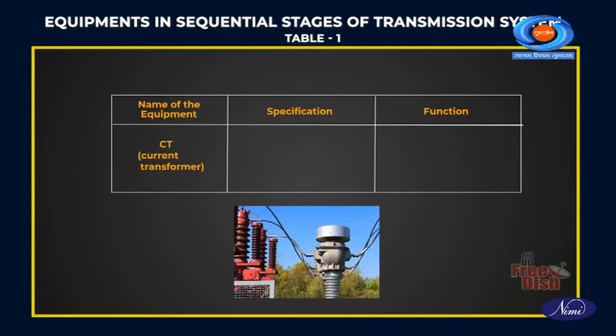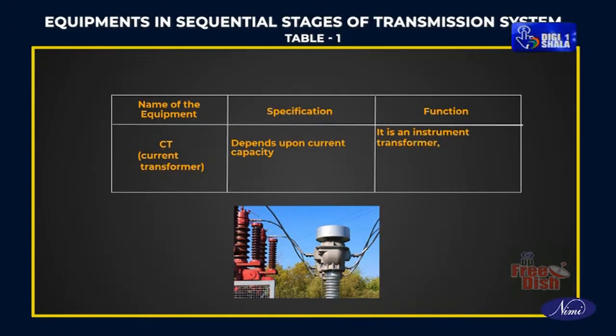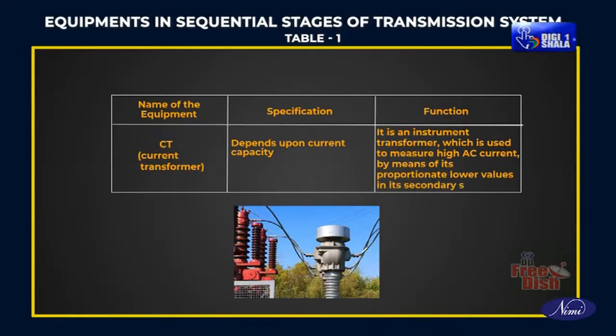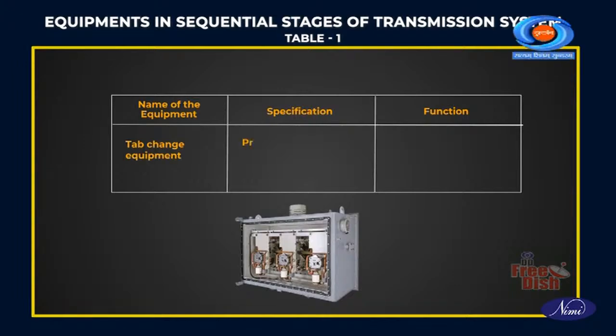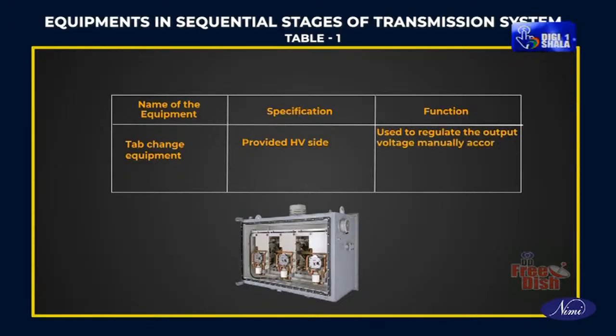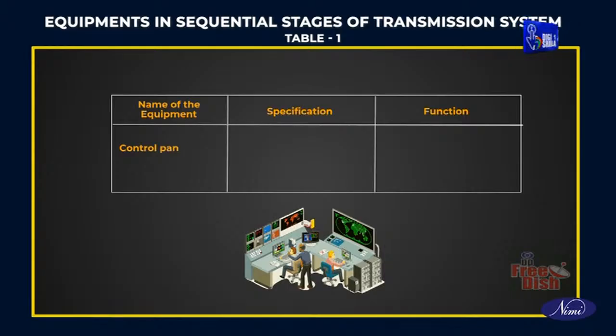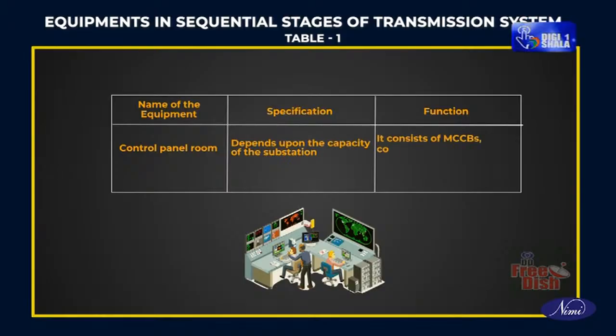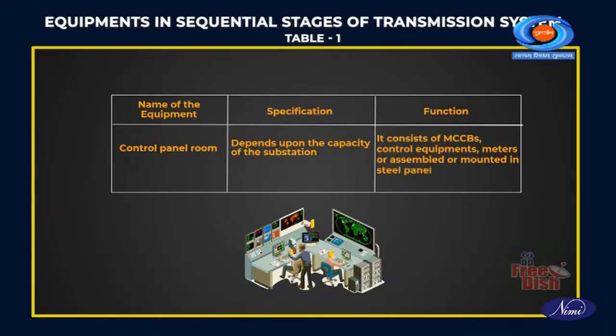CT or current transformer depends upon current capacity. It is an instrument transformer which is used to measure high AC current by means of its proportionate lower values in its secondary side. Tap change equipment provided HV side, used to regulate the output voltage manually according to the line voltages. Control panel room depends upon the capacity of the substation. It consists of MCCBs, control equipments, meters, assembled or mounted in steel panels in the control room.